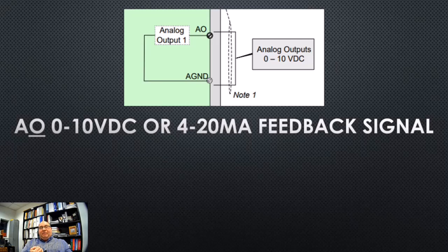Or if you have to go into one drive with 4 to 20 as an input, one of the disadvantages is you can't share that signal. It's only one signal for one drive, whereas with voltage, you could kind of splice into it. You could have 3 drives receiving the same voltage signal. So you take a 4 to 20, go to a drive with 4 to 20, come out 0 to 10, and then feed that to another drive if you had to branch off.